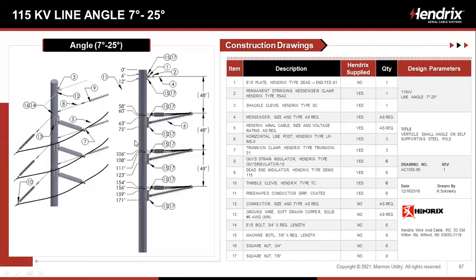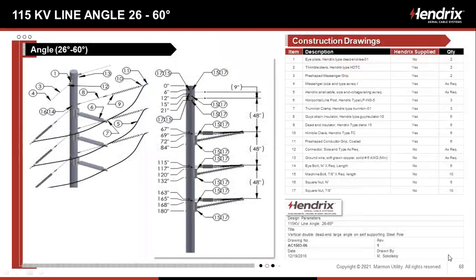Again, we don't want that conductor getting close to the pole. So we're going through the dead end grip on one side. We're pushing it away from the pole with a line post insulator, and then going back into the preformed dead end grip on the other side of the pole. There's going to be a heavier angle, 26 to 60, basically very similar construction.